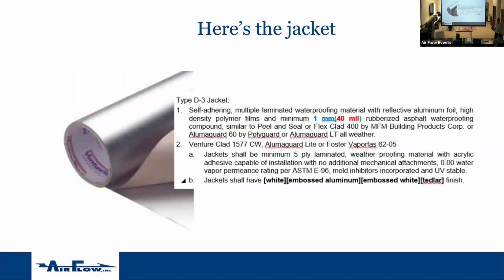Okay, then here's the jacket, a self-adhering, multiple laminated waterproofing material. This is called peel and seal. You have a long sheet, you pull it out and wrap it around, not the metal, but the insulation that's kind of floating on top, and then you take a squeegee and squeegee it. So it's sort of stuck to the insulation, but not necessarily. You glue the hard insulation to the metal, and then you put this on top of the rigid board. But if you have wrapped insulation, it's a little less sturdy. So this is actually a pretty good spec.